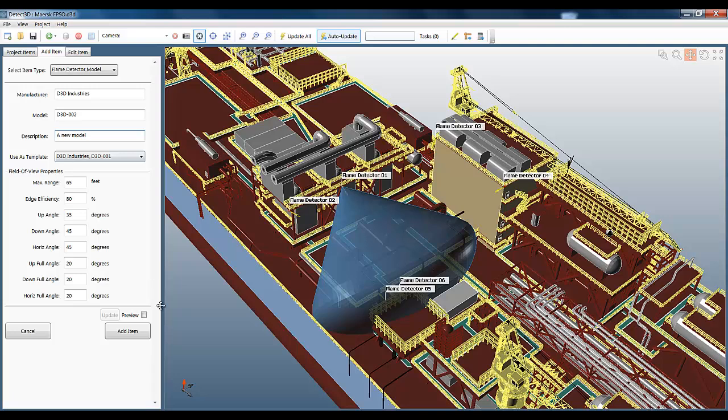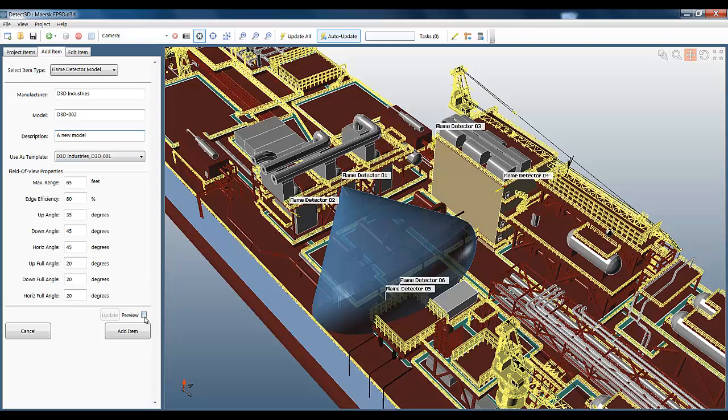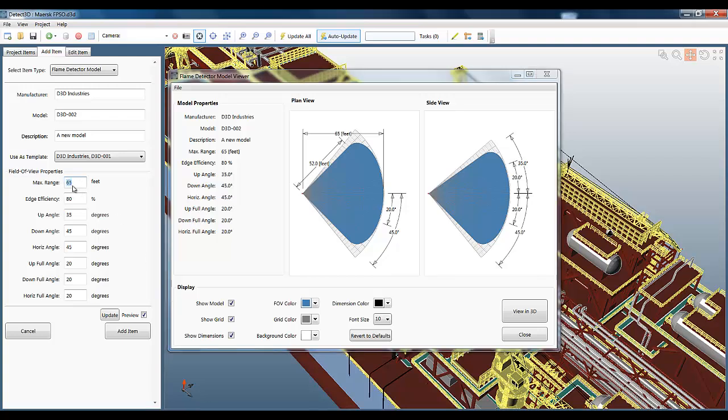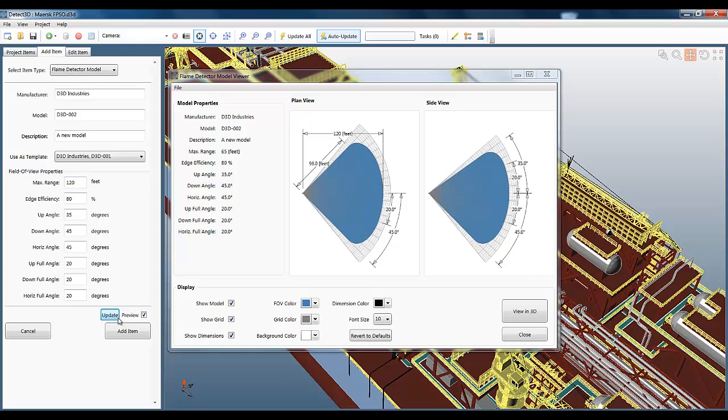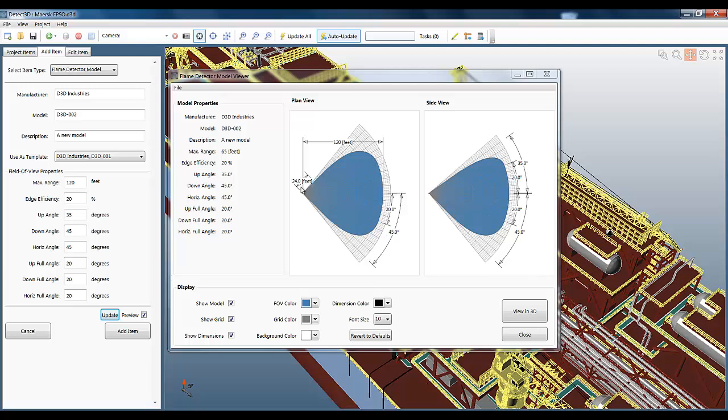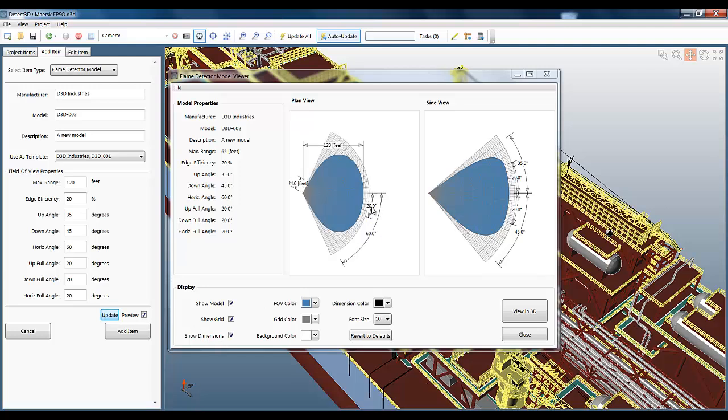Just change it to the fictitious D3D industries and call this one D3D002. I'm going to use the preview now to change certain parameters of the flame detector's field of view. Change the max range to 120 feet and update. You can see the preview's automatically updated there. Edge efficiency I'm going to change down to 20%, and this means that the drop-off is going to be greater towards the edges. You can see that here. I'm going to change the horizontal angle next. I'm going to select 60 degrees, so 120 degree full angle.